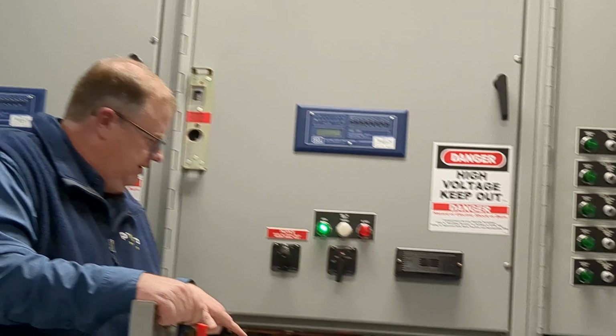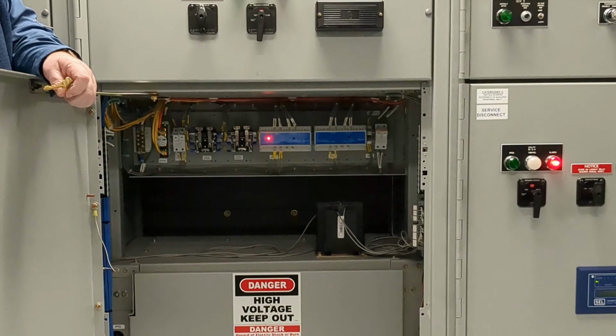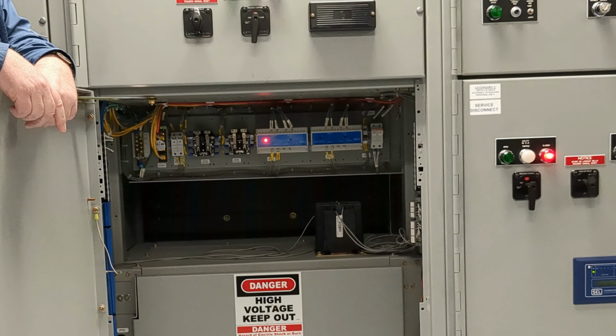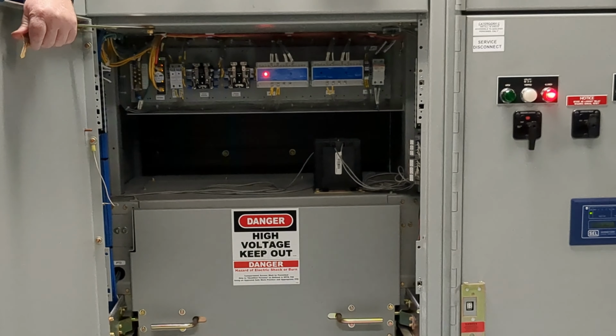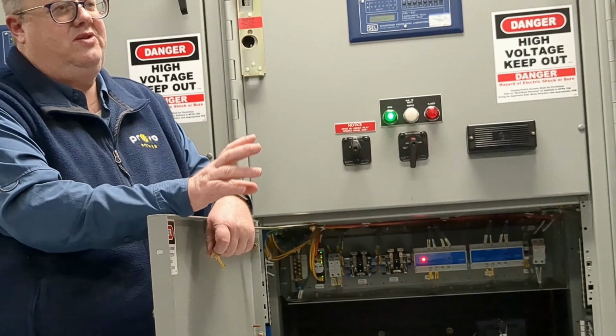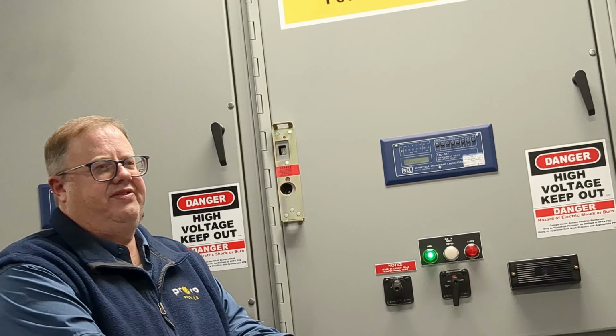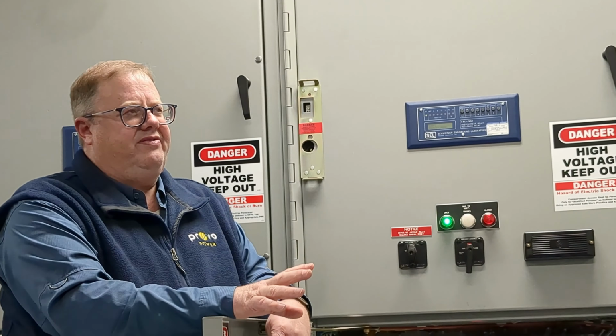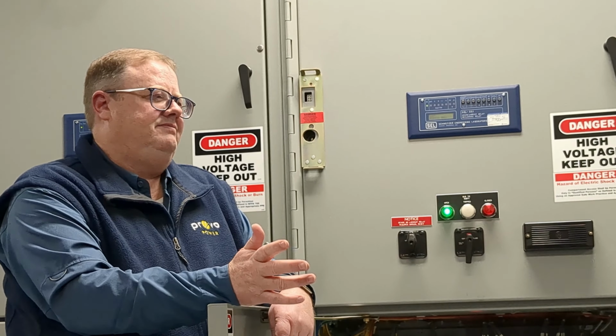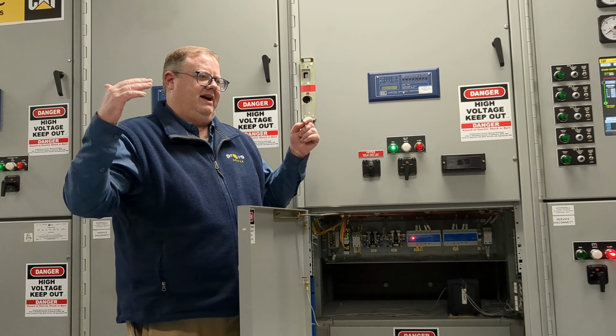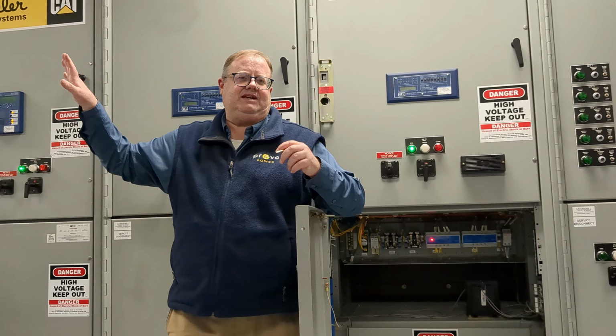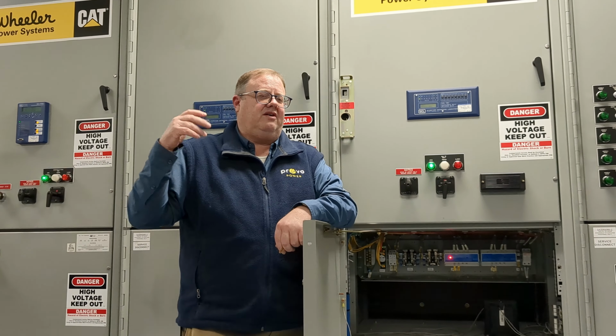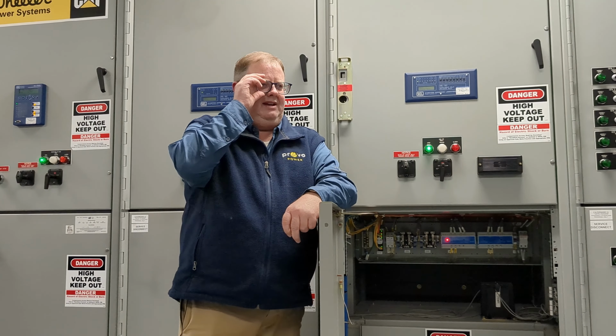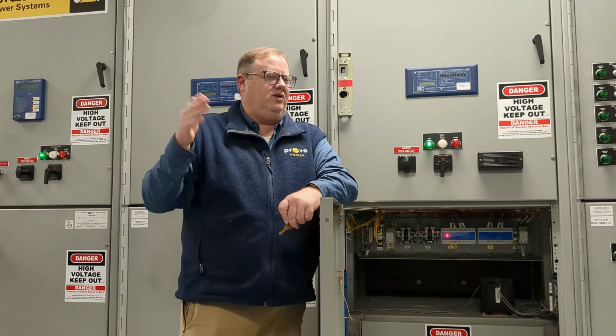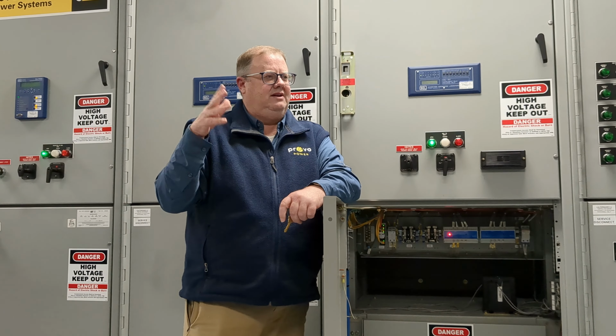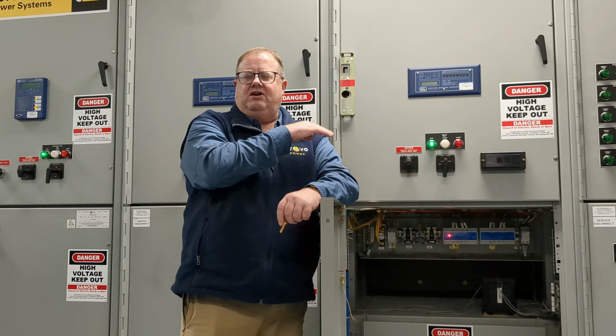This is a 12 kV breaker, so it'd just be like a breaker on your home, other than it can interrupt. It's either a 1200 amp breaker or a 2000 amp breaker. This is probably a 12,000 amps at 12 kV, right? So it's a big breaker. When you go outside, you'll see out in the substation, you'll see 46 kV breakers, kind of the same thing, but they break 46,000 volts, or a 138 kV breaker would be 138,000. In the switchgear, these are all 12,000 volts.